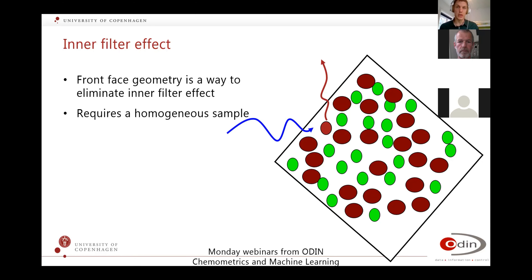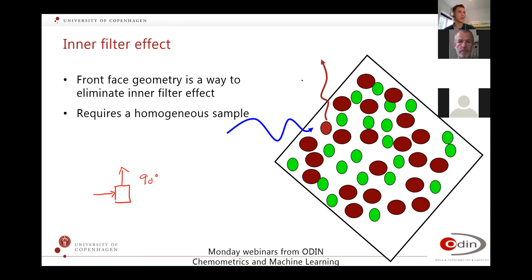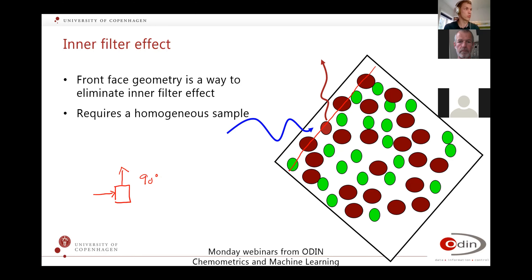One such solution is using front-face geometry. Instead of measuring at the regular 90 degrees — where light comes in and you measure what comes out at a right angle — you use a front-face measurement. What happens here is that you only measure part of your cuvette, mainly the surface of your sample. If you have a very homogeneous sample, that doesn't really matter because it will be representative. If it's a very heterogeneous sample, you start to get a problem with sampling.